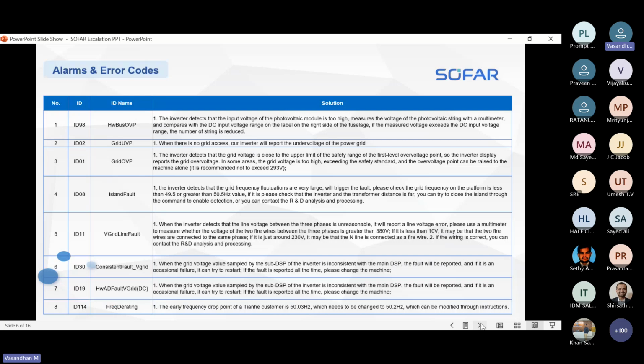So these are all alarm codes. Main alarm codes I will show in the PPT. ID 68, hardware bus OVP, nothing but the bus over voltage protection. So what we can check: the inverter detects that input voltage may be high, so we can check with the multimeter how much DC input voltage there is. This is the first step. Next step, when the voltage exceeds the rated voltage, then we can reduce the string. This is the solution. If we cannot reduce the string, we can provide other solutions also.